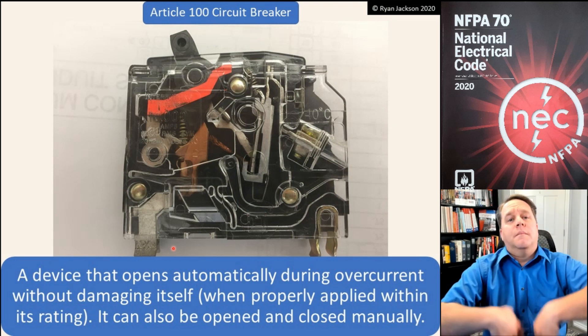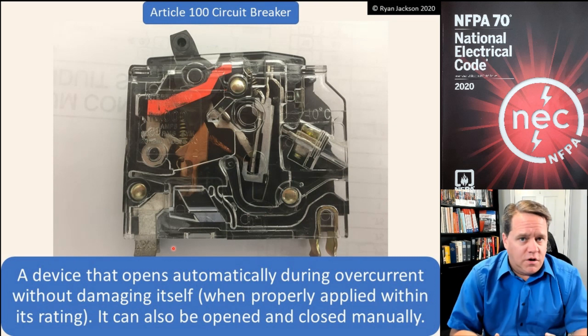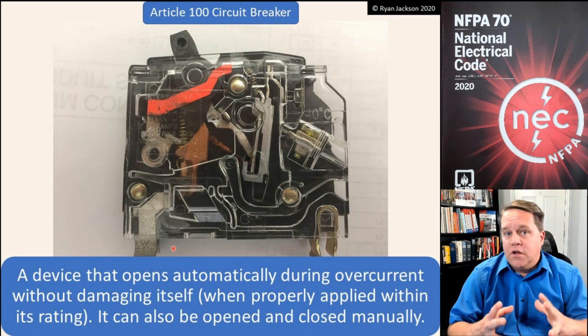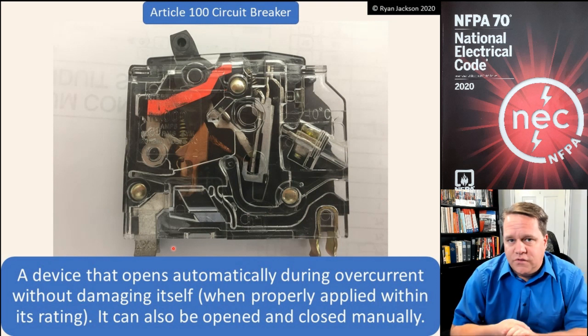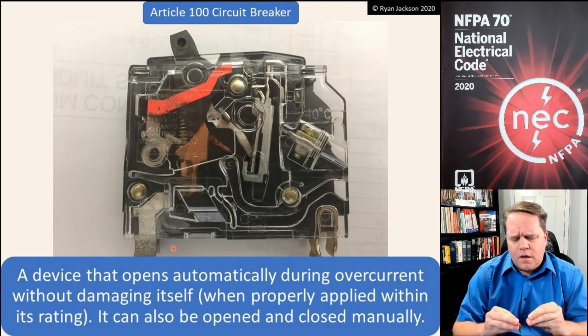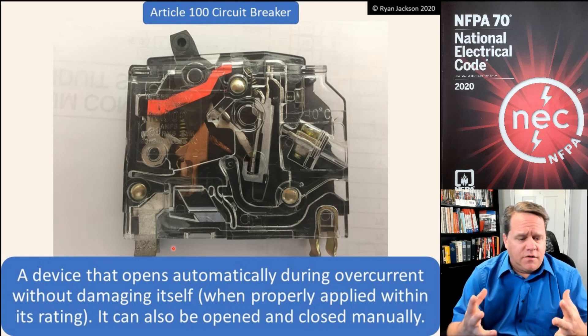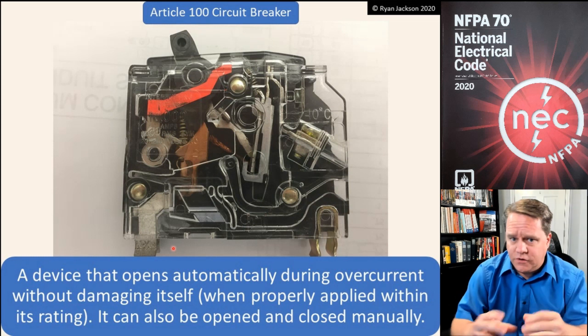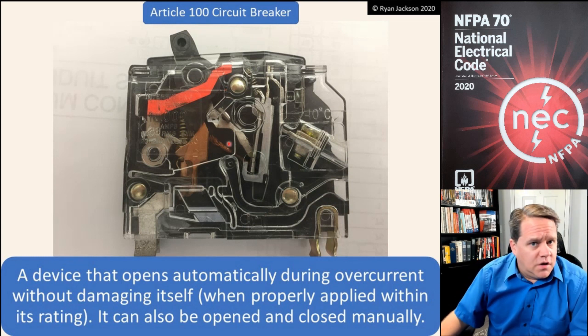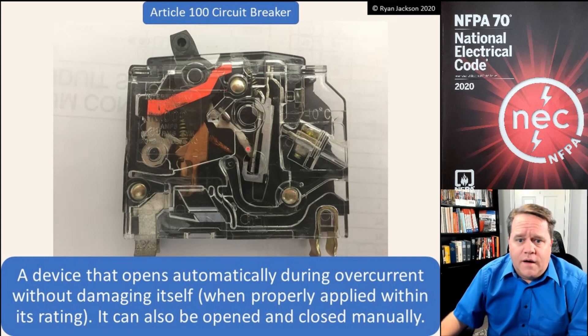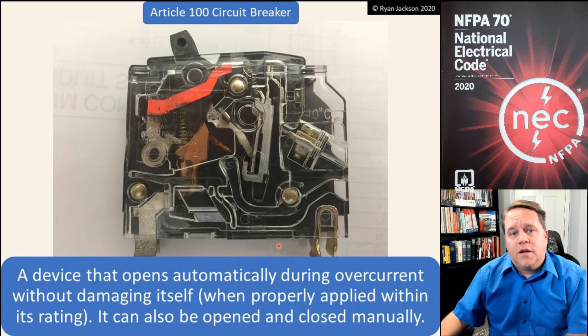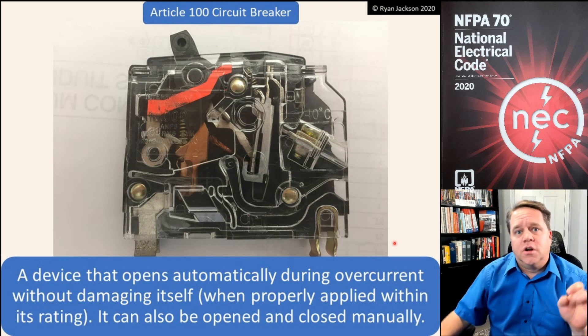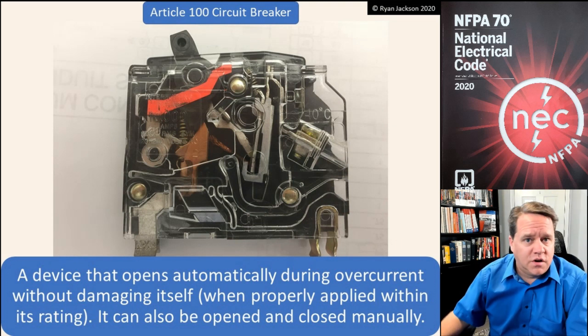The other part works off of magnetism. When we have a ground fault or a short circuit, that is a massive amount of current — often in the thousands of amps. We have this massive expanding and collapsing magnetic field, and that causes the contacts to open as well. So we have the magnetic portion for faults and the thermal portion for overloads — the thermal magnetic circuit breaker provides protection against overloads, ground faults, and short circuits.